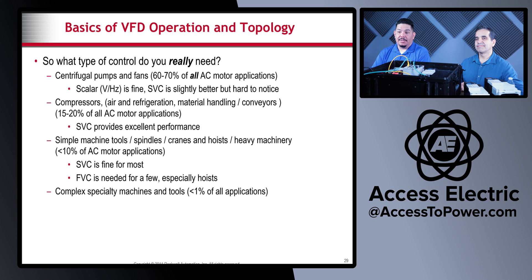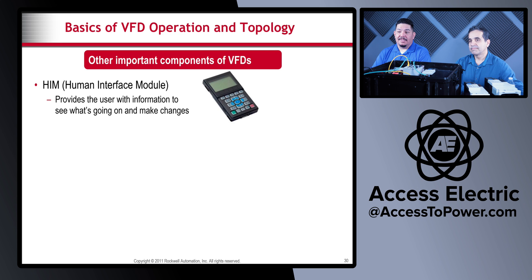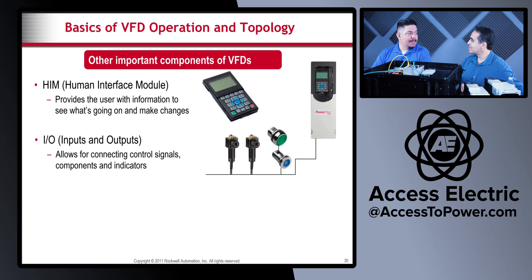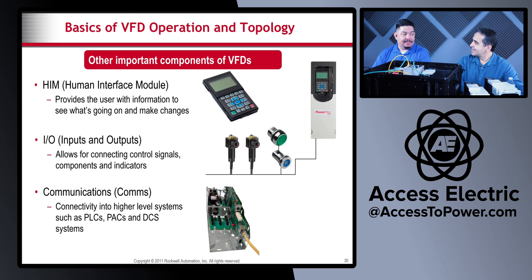Besides the internal electronics, other important VFD components include the HIM (human interface module), which provides the user with ways of setting up parameters inside the VFD. There are also I/O — all drives have inputs and outputs that can be used for control; you can hook up sensors to the terminal block, and the VFD can act almost like a small PLC. The communications module is increasingly important — Ethernet capability, especially with PowerFlex drives, allows you to remotely program drives, monitor their output, and display status, faults, and speeds on an HMI.